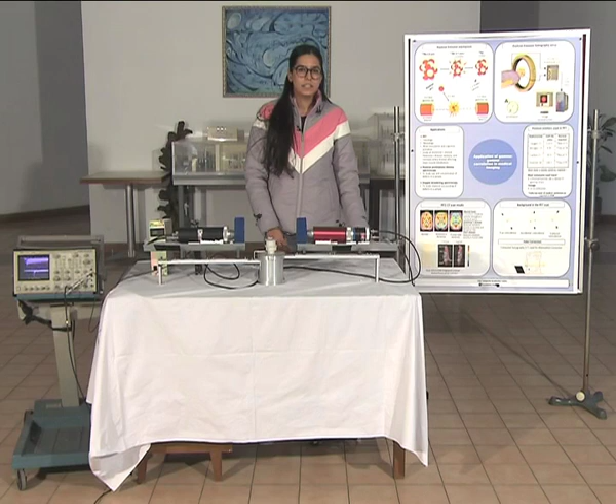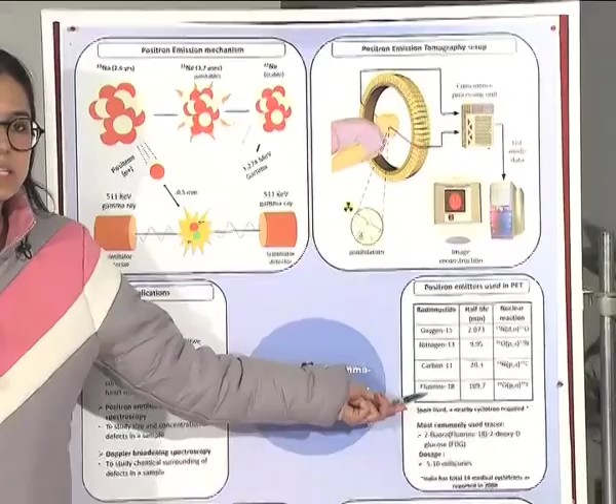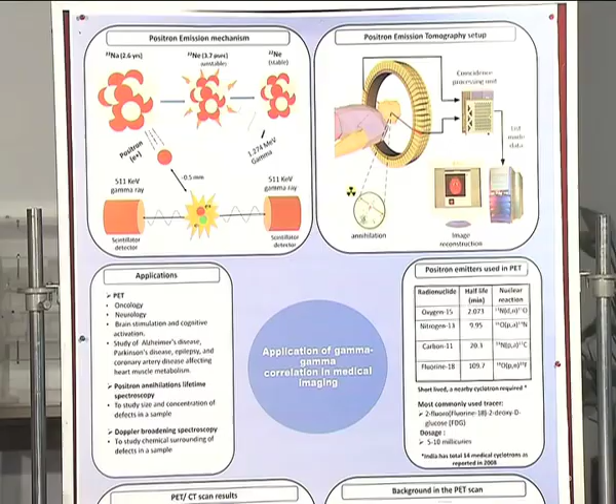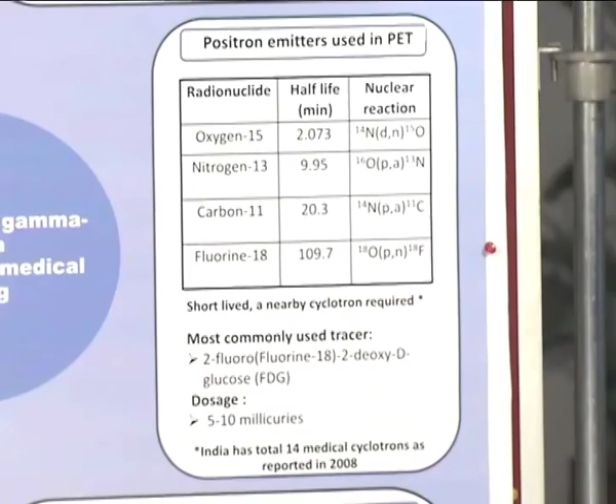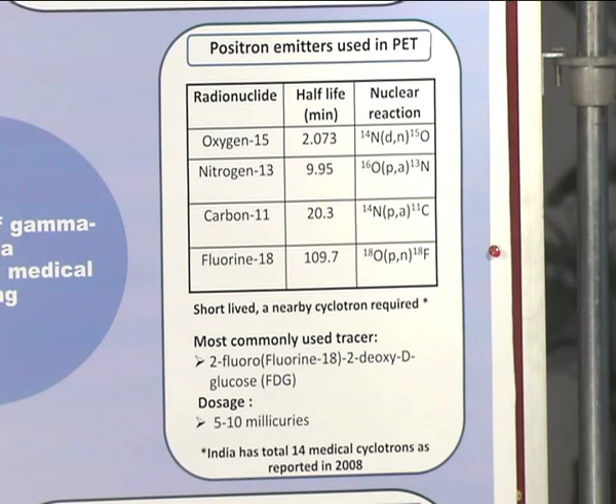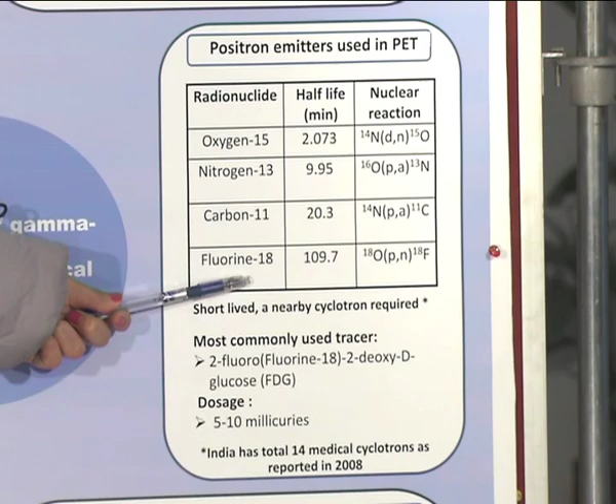The setup is similar to what has been used here, except for an integrated set of detectors and a sophisticated processing and imaging technique. However, for injection of the radionuclide into the human body, we cannot use this particular source. So we use an 18 fluorine source, in the biological form of fluorodeoxyglucose, and the minimum dose injected into the human body is around 5 to 10 millicurie. These specific sources are synthesized in nearby cyclotrons, and this radionuclide has a half-life of 109.7 minutes.